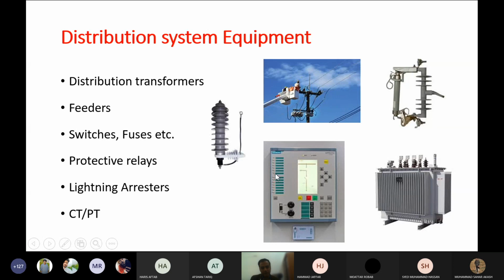This is the protective relaying equipment. This is the protective relay. Recently, digital and microcomputer-based relays are installed in the distribution stations. These computer-based relays can perform all the functions of under frequency, over frequency, under voltage, and over voltage relaying. Before that, different types of relays were installed. For over frequency, you had to install over frequency relays, and for under frequency, under frequency relays. But after the arrival of computer-based relaying, all these relaying processes, whether due to over voltage, under voltage, over frequency, or under frequency, are performed through this computer-based relay.